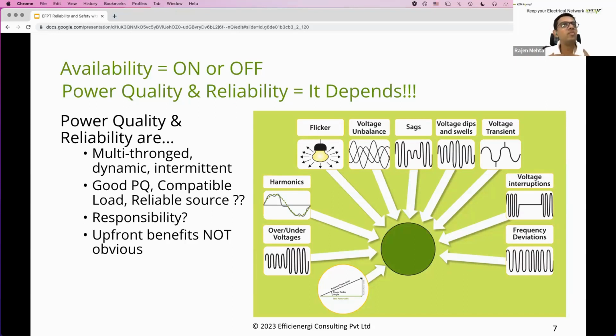Rameshji, we do not manufacture harmonic filters, otherwise we would not be very different from other filter manufacturers who also do studies. We are purely a neutral, third-party auditing agency who looks at the customer's interest first, to understand whether or not harmonics is a problem in the first place. If it's not, we'll tell you plainly, please do not do anything. If it is, we'll recommend the configuration, type, and capacity parameters of the harmonic filter you can use to approach reputed manufacturers.